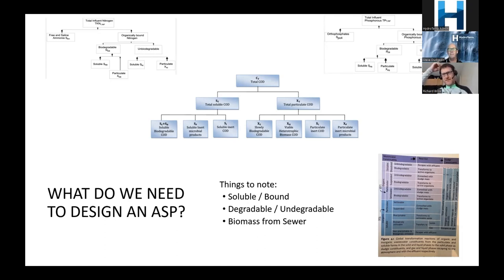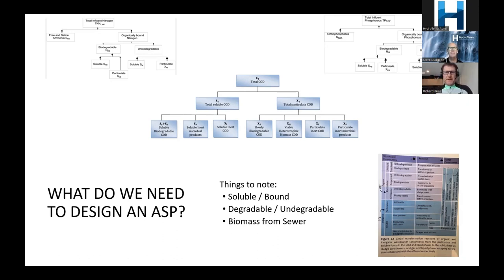Going back to BOD — BOD₅ is the five days to get down the Thames, BOD₇ is seven days to get down the Seine, and 21 days is a fjord in Norway. You could have two samples with exactly the same BOD₅ that will do completely different things in your treatment plant. Doing a proper fractionation and getting proper data using automatic samplers and online instruments is a massive way of both optimizing your plant and reducing the capital cost of your asset.